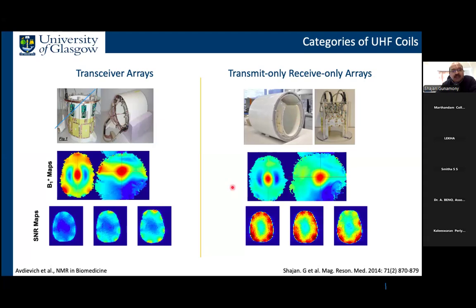So the field produced by this design approach is weaker in the periphery. You have this constructive interference in the center, but it is weaker in the periphery. That's because you need space to place a receiver array. But if you look at the signal to noise ratio, that's what we really want. And if you look at the signal to noise ratio, you see it's so much better than these transceiver arrays.